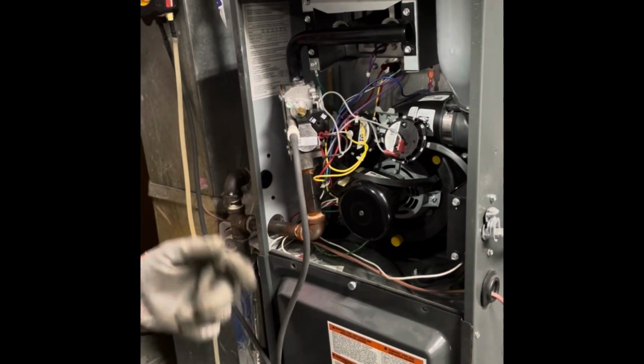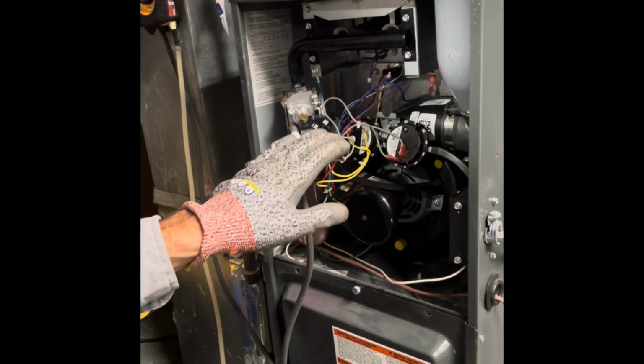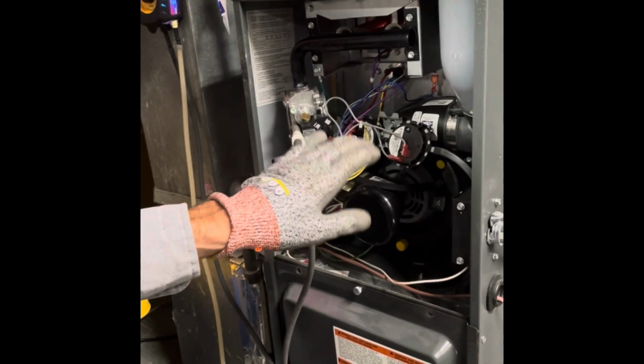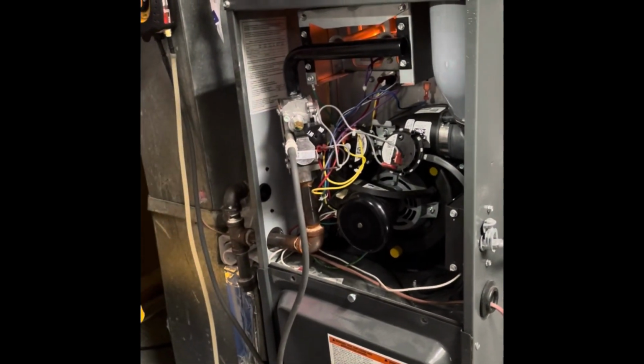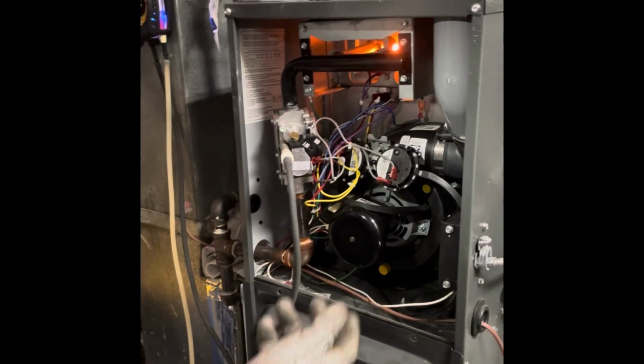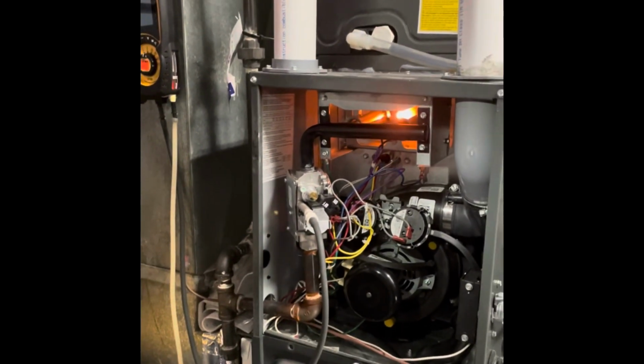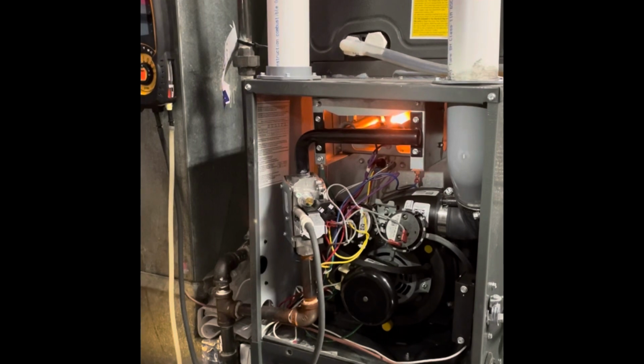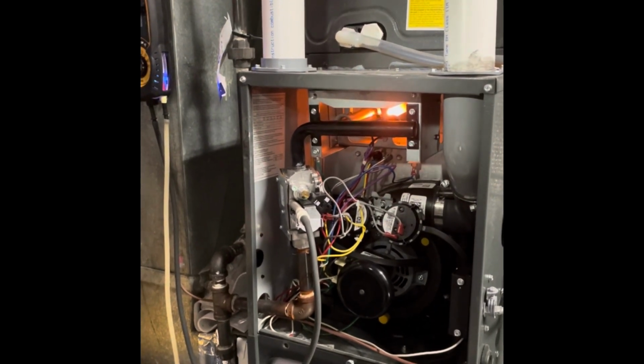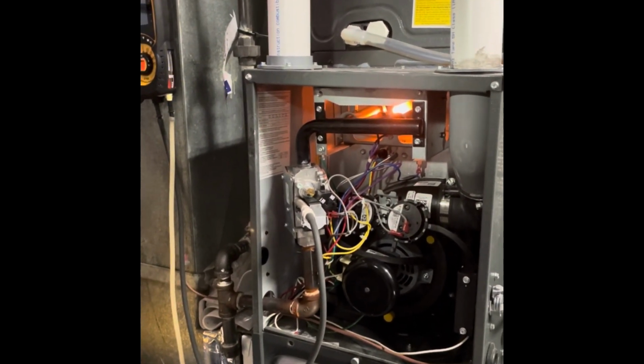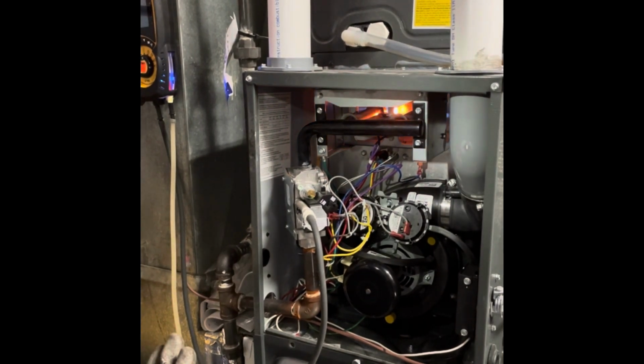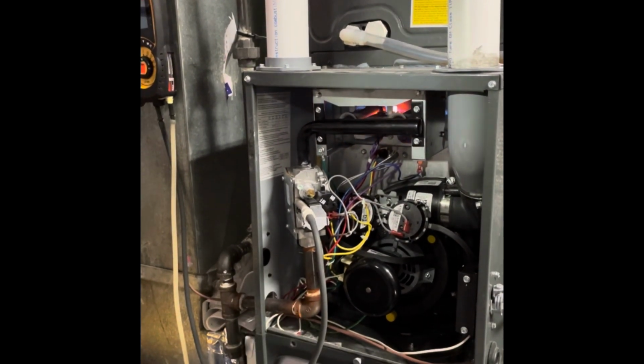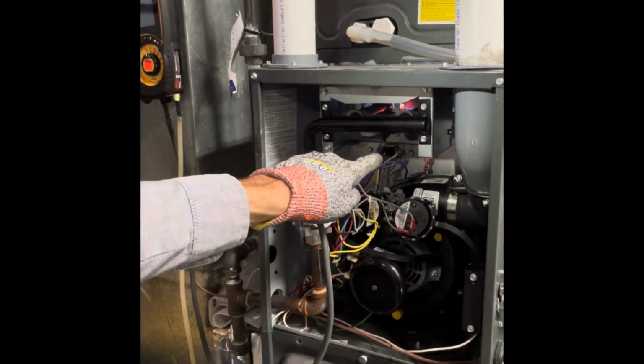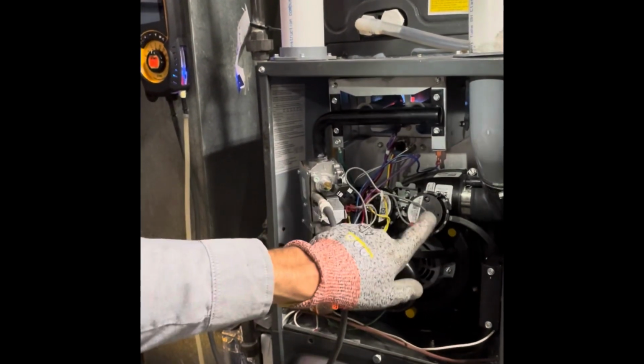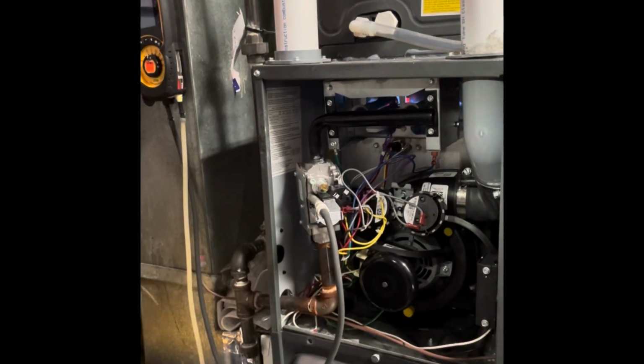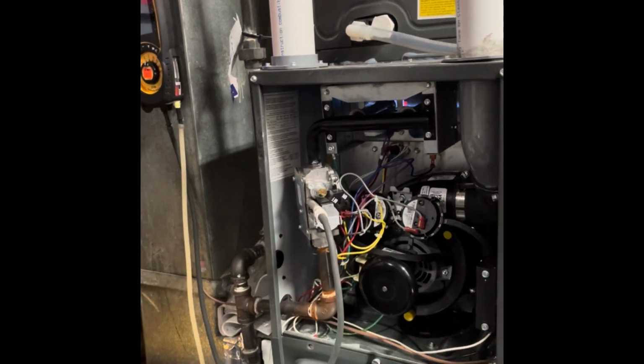This thing's going to try to start back up. It'll make sure that pressure switch is closed. If this switch isn't closed, we're not going to have the burners ignite. Because I did test the safety, I want to make sure it didn't fail in the process and that it is still working. So we'll just wait a second. Okay, so burners are on. I usually count 4 seconds just to make sure we're satisfying the flame sensor and our pressure switch is remaining closed, which will give him great heat in his house.